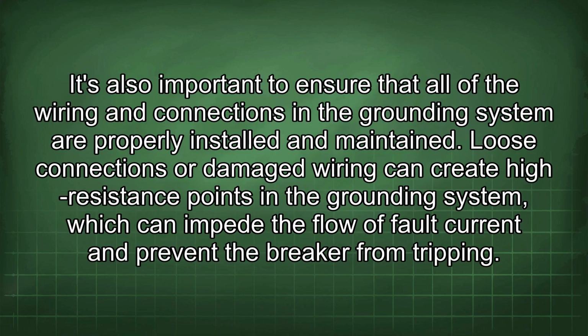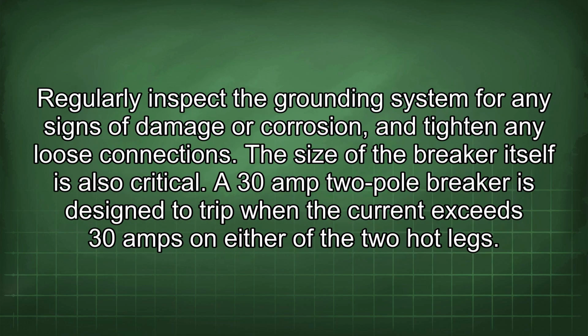It's also important to ensure that all of the wiring and connections in the grounding system are properly installed and maintained. Loose connections or damaged wiring can create high resistance points in the grounding system, which can impede the flow of fault current and prevent the breaker from tripping. Regularly inspect the grounding system for any signs of damage or corrosion, and tighten any loose connections.